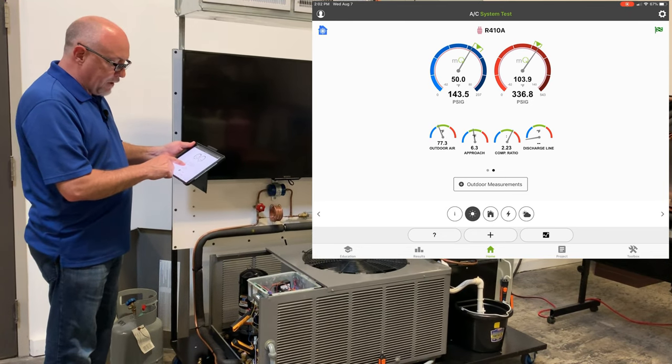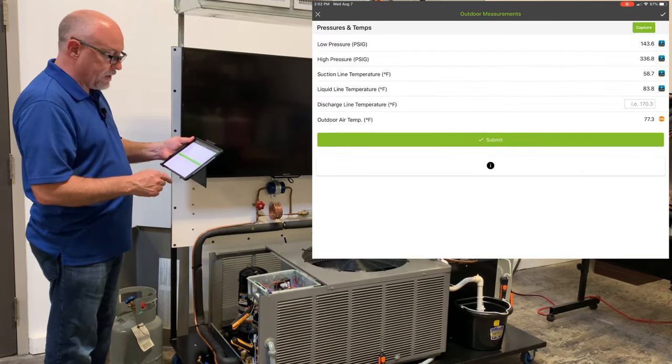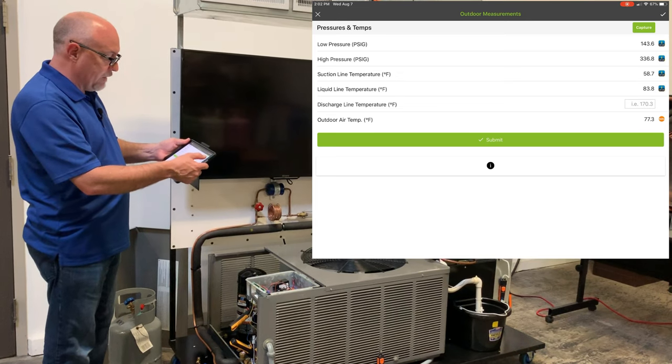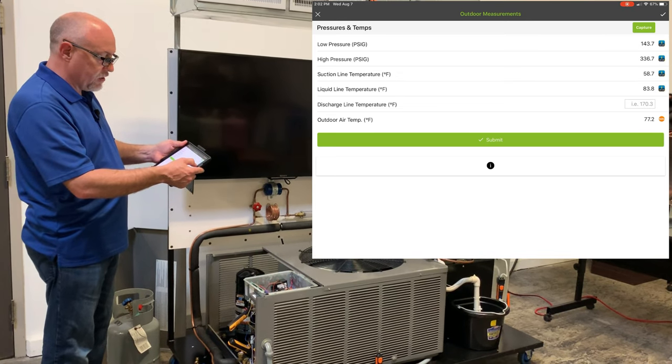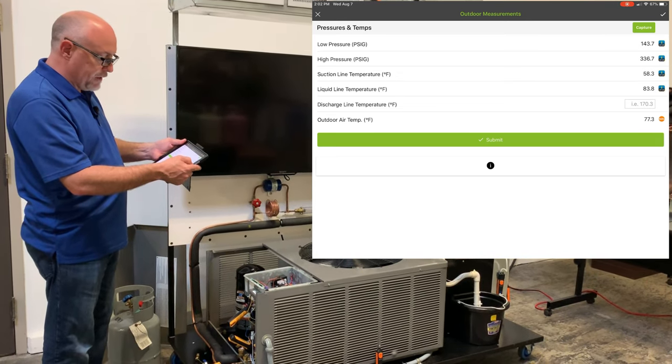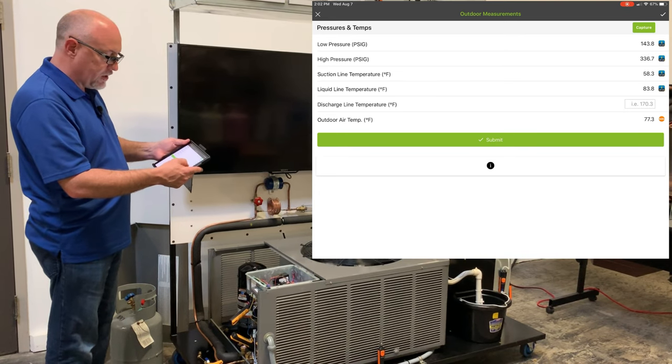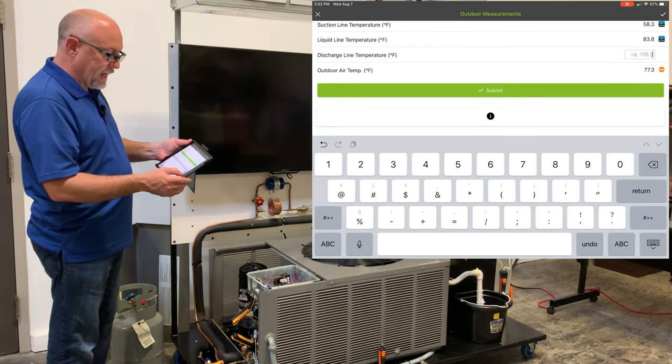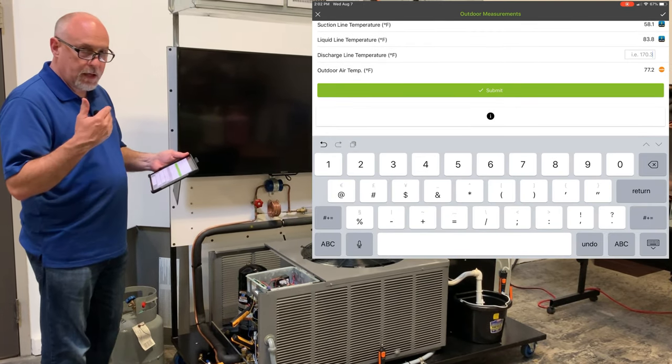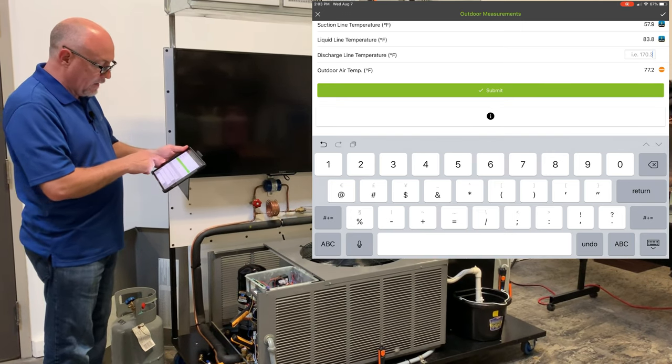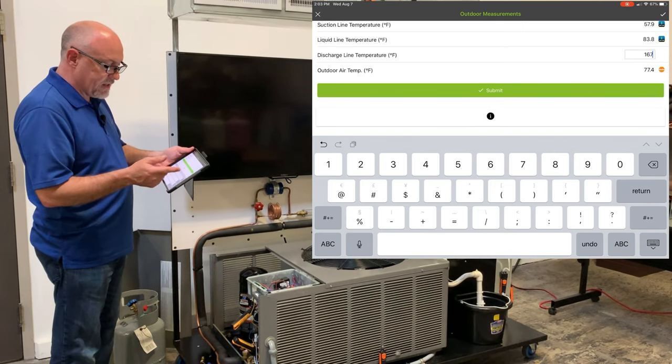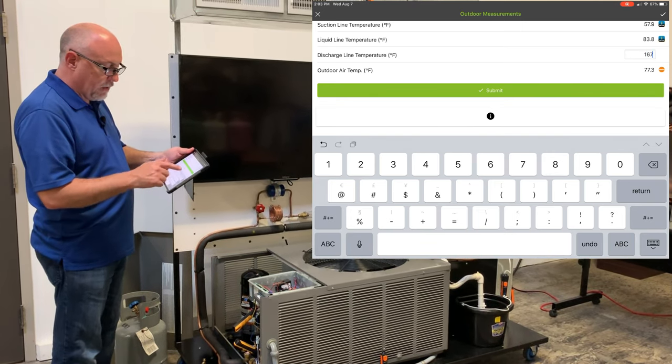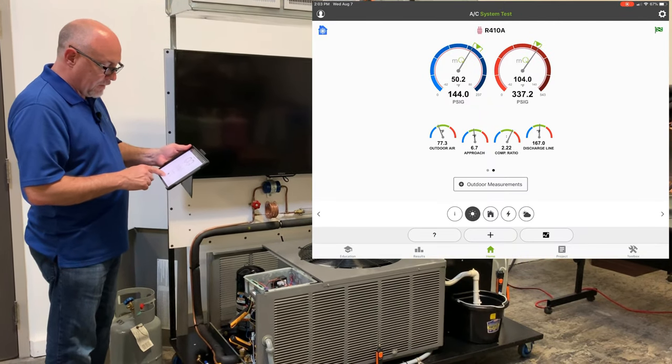Now if I tap on the big button for outdoor measurements, I can see my low pressure, my high pressure, my suction line temperature coming off of the Fieldpiece probes, my outdoor air temperature coming off testo, and then I have a user input box here. So I had another thermometer, maybe an analog thermometer I wanted to enter in a discharge temperature, let's say 167, it would allow me to do that and hit submit.